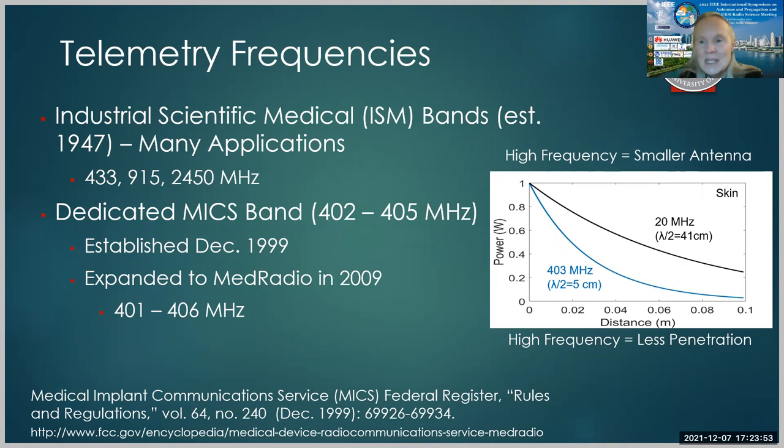So the frequencies that are feasible for this application are either the industrial, scientific, medical bands, 433, 915, or 2450 megahertz, or the dedicated MICS medical implant communication services band from 402 to 405 megahertz. This was established in 1999 and expanded to the med radio band in 2009, so 401 to 406 megahertz. So you're going to hear me talking about these two bands and the 433 megahertz that's close by.